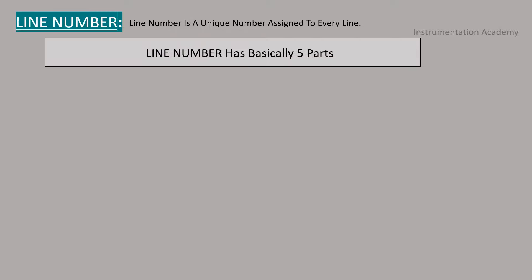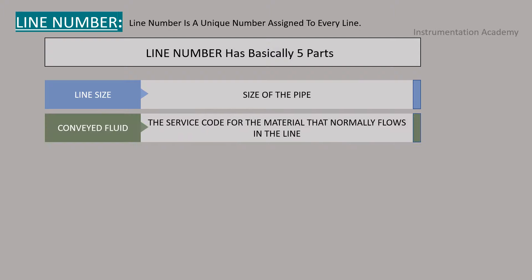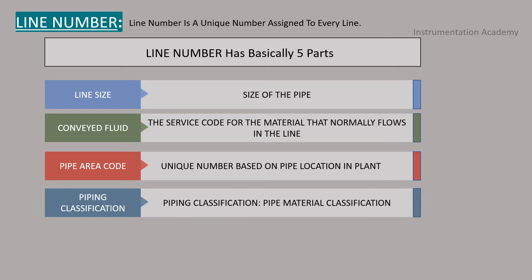Line number. Every pipe on a P&ID requires a unique number so that it can be uniquely identified during design or referenced in operating procedures. Line number is a unique number assigned to every line. Line number has basically five parts. First part is line size. It represents the size of the pipe. Second part is conveyed fluid. This is a service code for material that normally flows in the line. The third part is pipe area code. It is a unique number based on the pipe location in a plant. Fourth part is pipe material classification and the fifth one is insulation code and thickness.